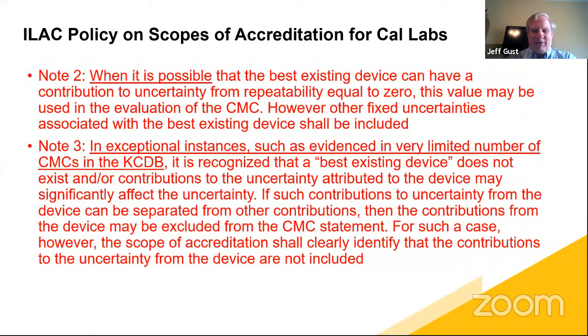which contributions may not be included in that particular process as well. So, another area I can think of is when you're doing measurements on the Josephson voltage system. Generally, the world's best traveling artifact that you can use between Josephson voltage systems is the Fluke 732. But even the Fluke 732 is noisier and has much more of an uncertainty contribution than the Josephson voltage system. So other than being able to pick up and move one Josephson system to the next place, which they're starting to do now, they need to understand that there are sometimes these issues to address.